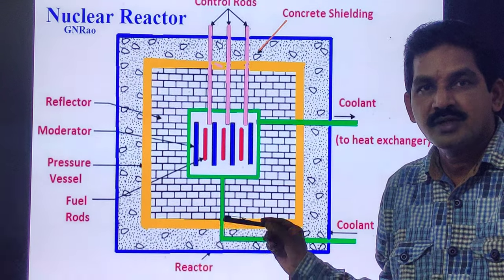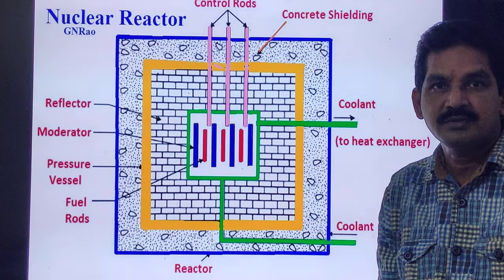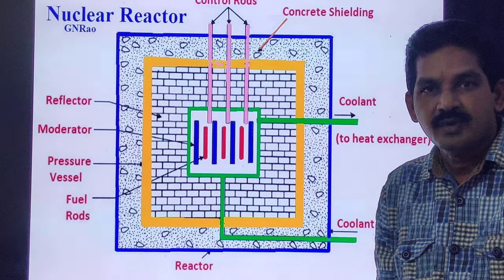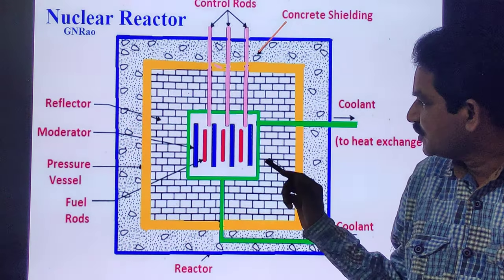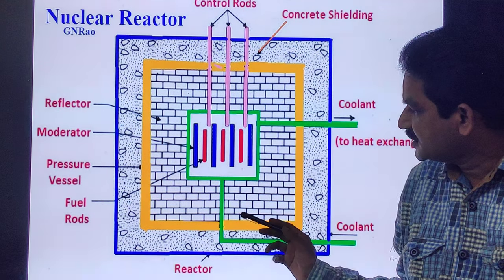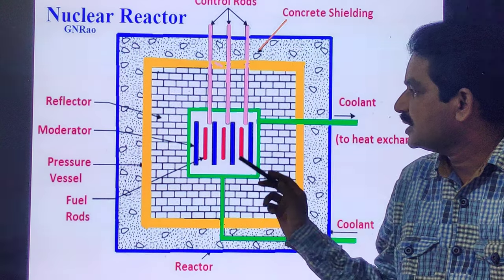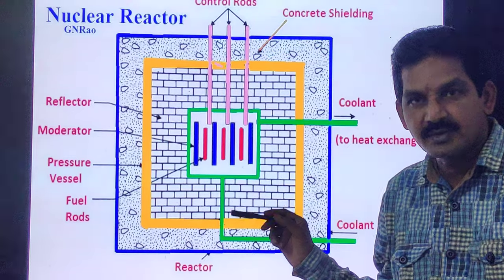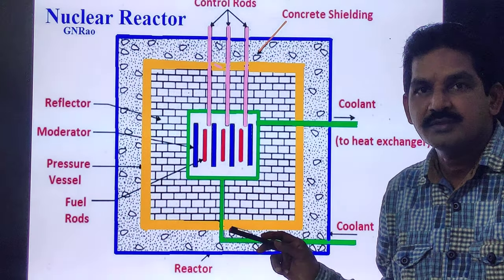The assemblies are exactly placed in the reactor according to the fuel loading pattern. The core is located inside a reactor pressure vessel and is carried by a core support barrel. A bottom plate of the support barrel is called lower core plate. This structure consists of N holes for fixing fuel assemblies, where N is the number of fuel assemblies in a specific reactor.